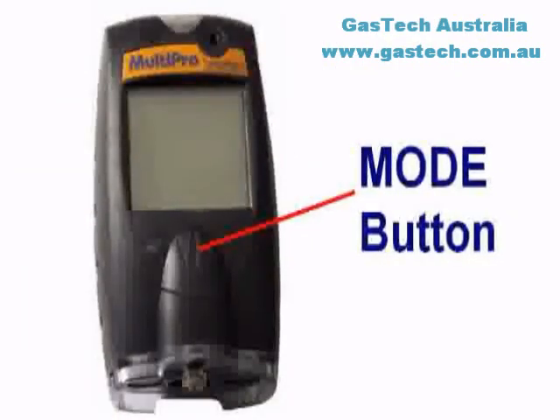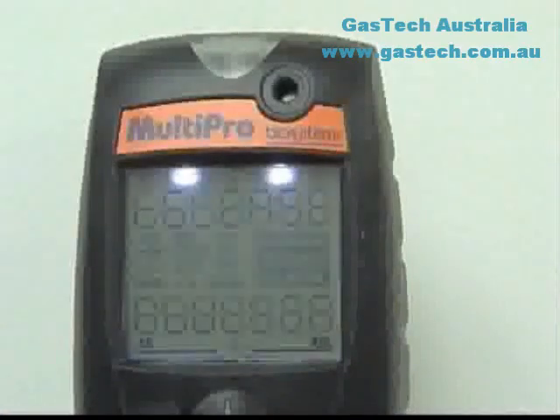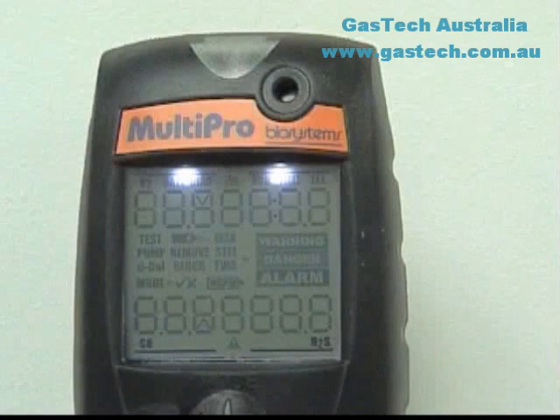The mode button is located on the front face of the instrument and controls all procedures necessary for day-to-day use, including initiating the automatic calibration sequence. To turn the instrument on, just press and release the mode button. The Multipro will automatically proceed to the LCD test screen. At this time, all sections of the LCD screen should be lit.